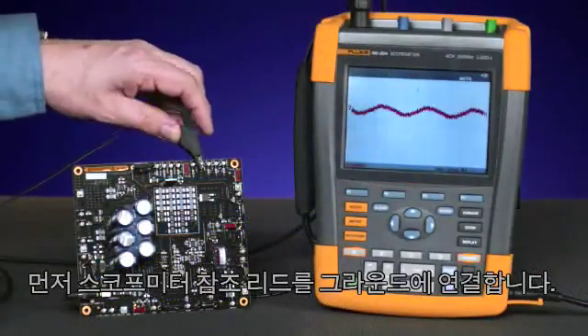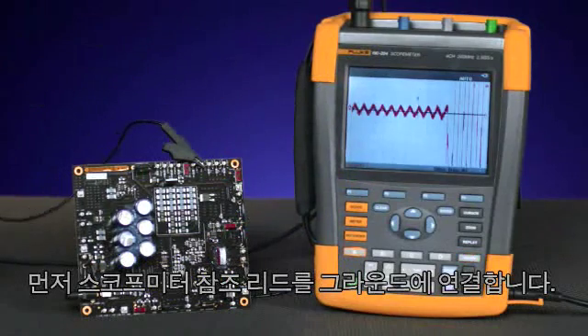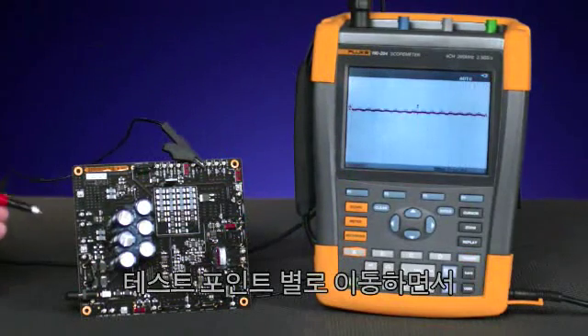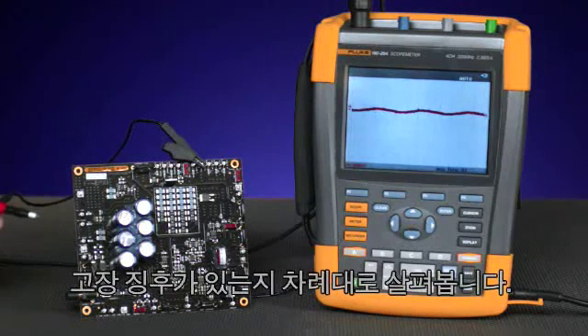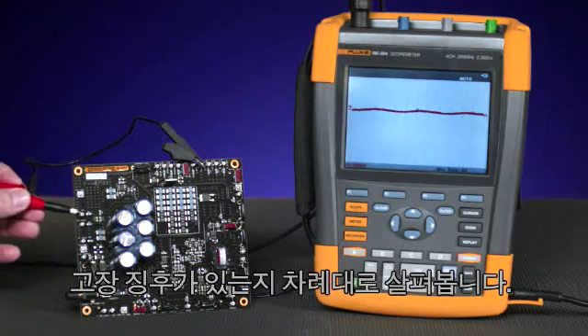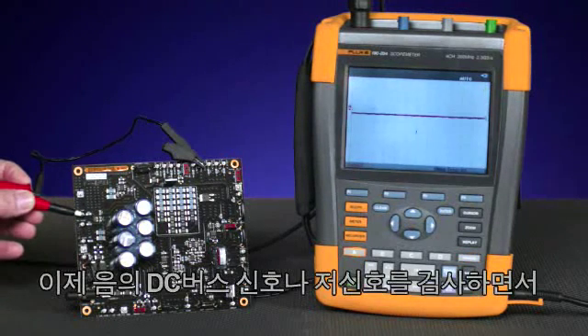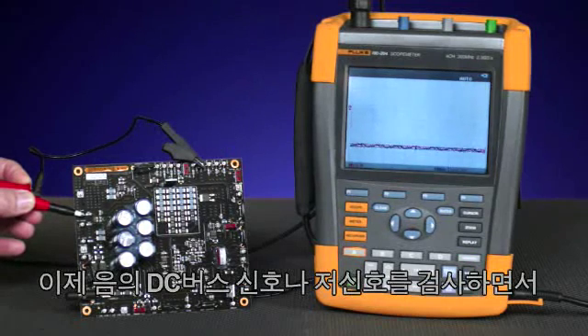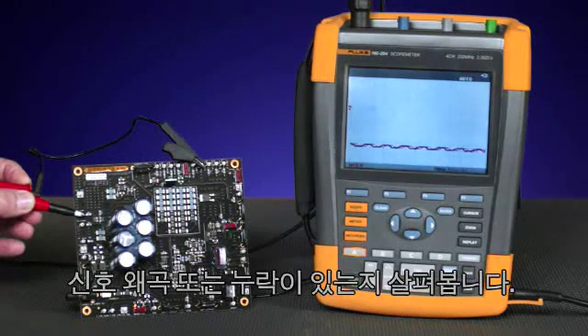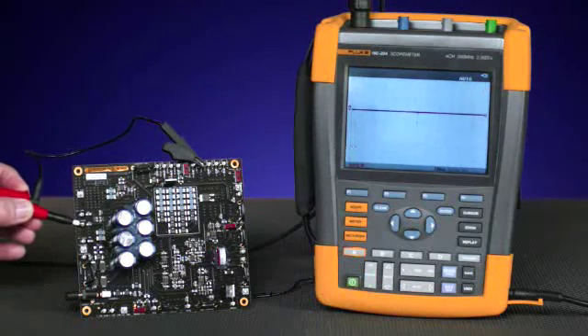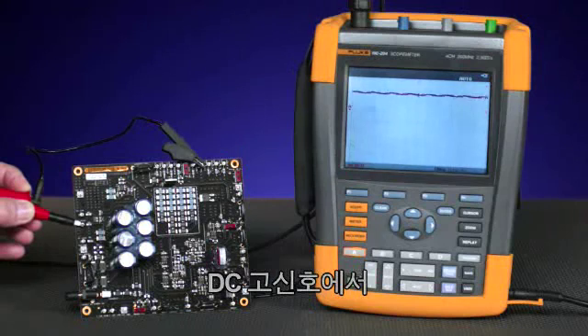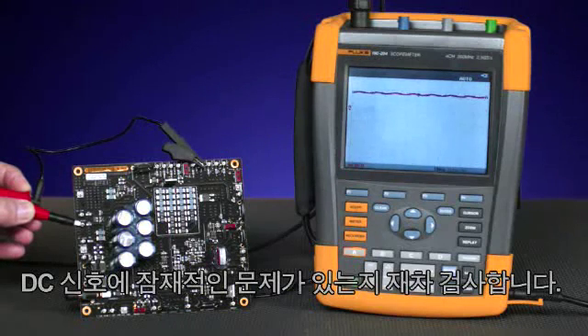First, you're going to connect the ScopeMeter reference lead to the ground plane. Then you can move from test point to test point, looking at each of the critical test points for signs of failure. Here, I'm probing on the DC bus negative or low signal, looking for any signs of distortion or dropout of the signal. Moving to the DC high signal, again, inspecting for any potential problems on the DC signal.